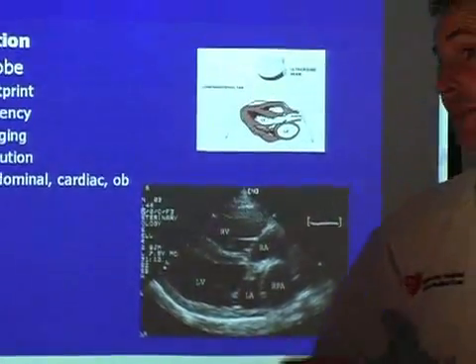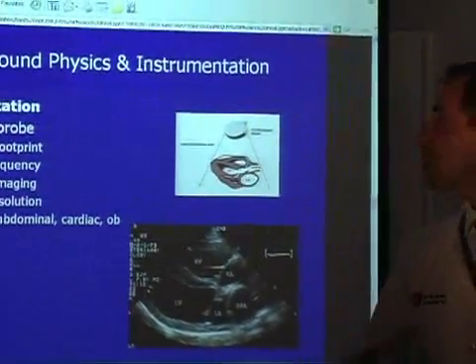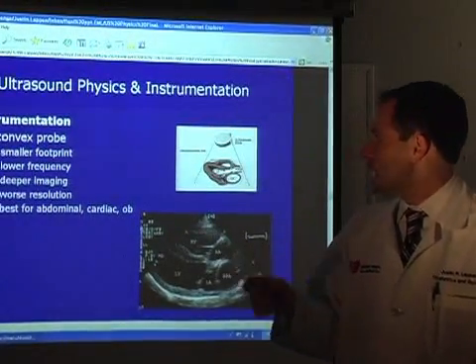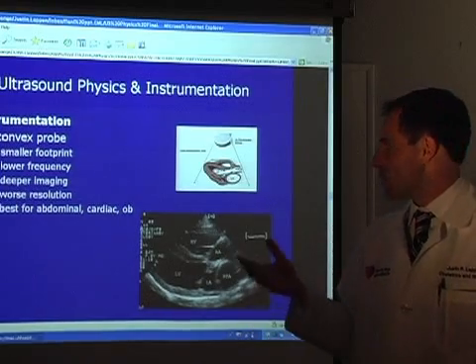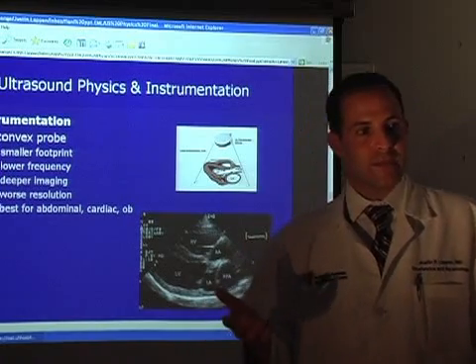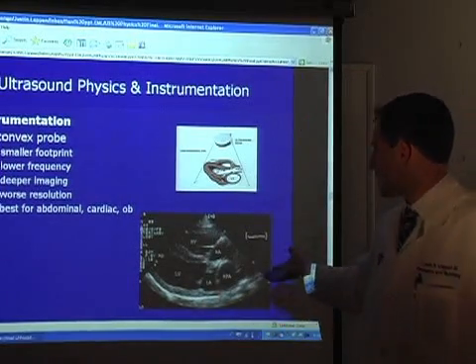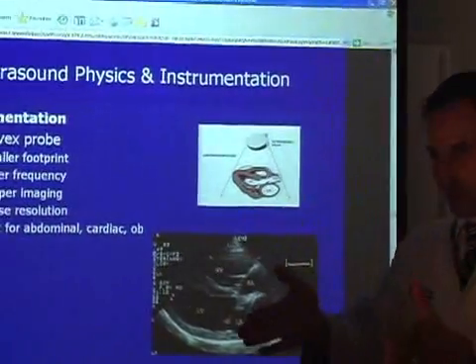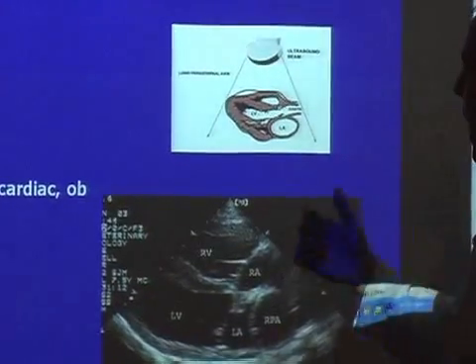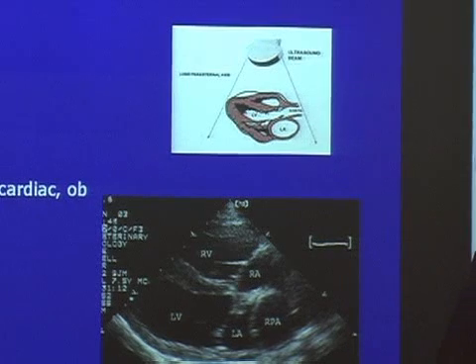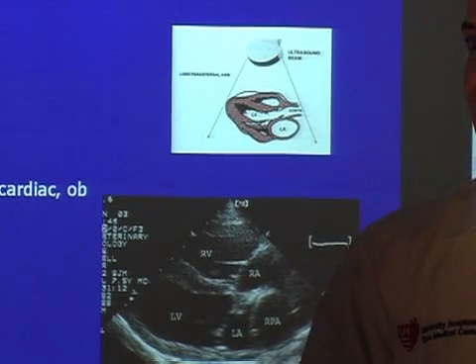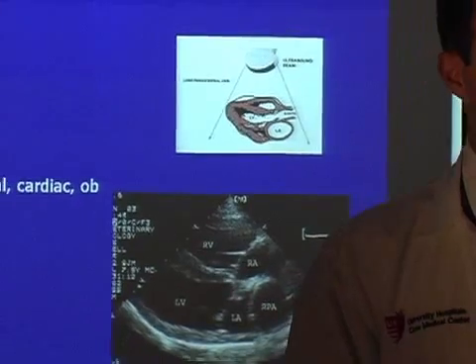The convex probe is the one you're more commonly going to see on labor and delivery or with echocardiogram. It uses lower frequency, has a smaller contact area with the patient, a smaller footprint, but it allows for deeper imaging. The resolution is not going to be exactly the same as with soft tissue imaging, but it allows you to visualize deeper structures. This is what you would typically use for abdominal imaging, right upper quadrant ultrasound, obstetrics, and cardiac procedures.